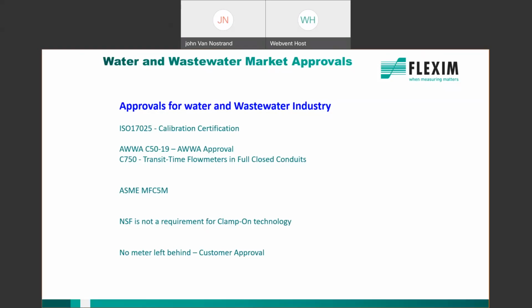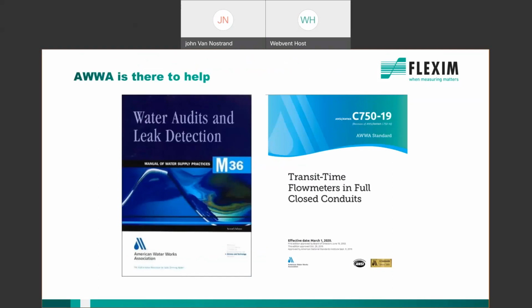So I'm also often asked if FLEXIM meets the NSF standard. The answer to that is basically no. We don't have to, because we clamp onto the outside of the pipe. None of our components actually touch the drinking water, so it's not a concern at all. AWWA M36 is the handbook for water resource management, which we meet, and all of our ultrasonic meters cover the C750 for water and wastewater as well.